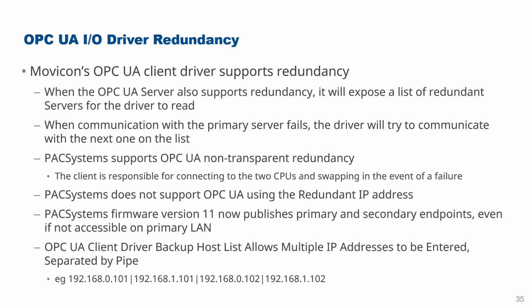So with PAC Systems PLCs, this is implemented using OPC-UA non-transparent redundancy. The way that works is the client is responsible for connecting to the two CPUs and swapping in the event of a failure. The opposite is transparent redundancy, where the servers, the PLCs, are responsible for performing the swapping and so on. So in the case of PAC Systems PLCs, we do support OPC-UA non-transparent redundancy, both in Movicon and in the PAC Systems range. And then that automatically works. It's just a matter of configuring that, and then having the appropriate networking architecture, and then it will automatically swap over.